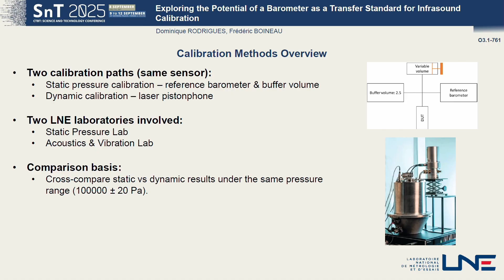Okay, so here, now, this is not the figure. I apologize. I normally have another figure, so I will comment. Here is normally the result for the static pressure calibration. The calibration cycle was performed with 2 Pascal steps, starting from the 1,000 hectopascal, increasing by 20 Pascal, decreasing by 40 Pascal, and coming back to the initial static pressure.